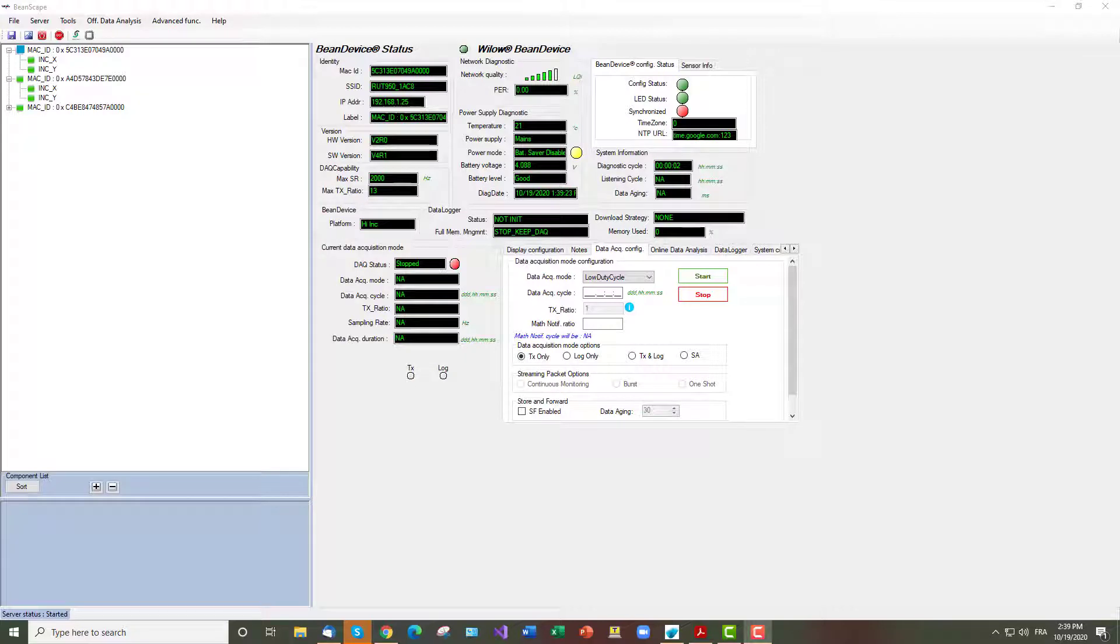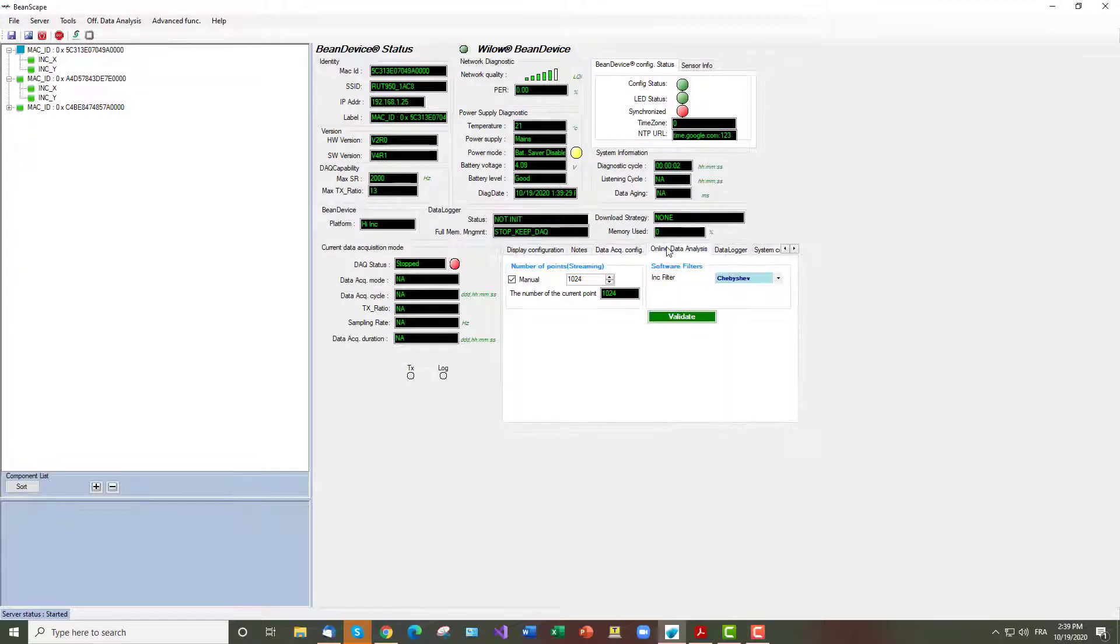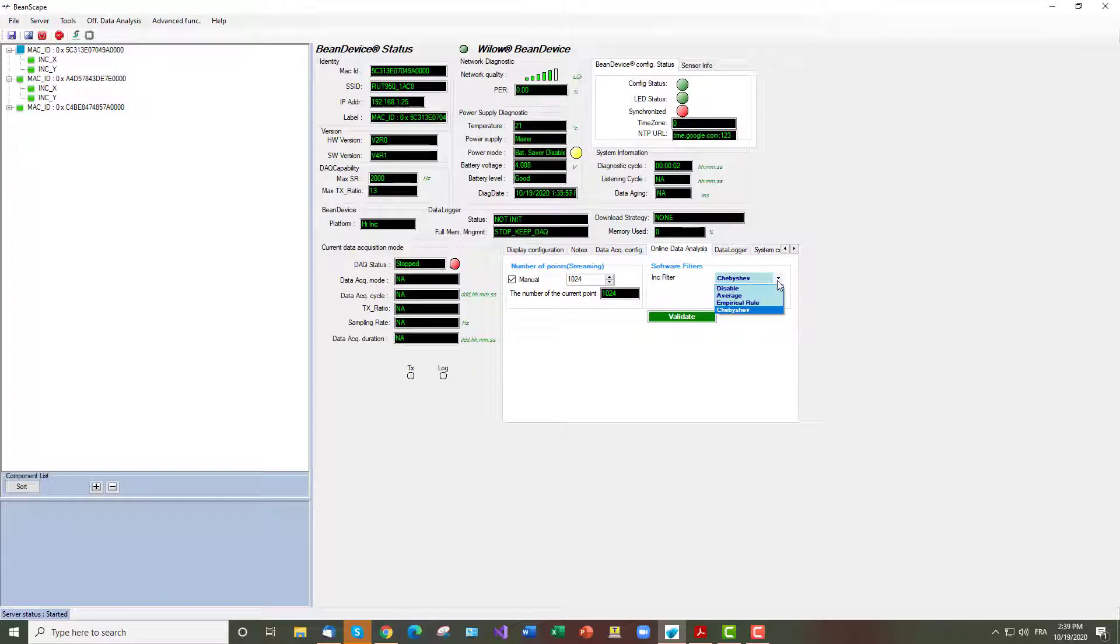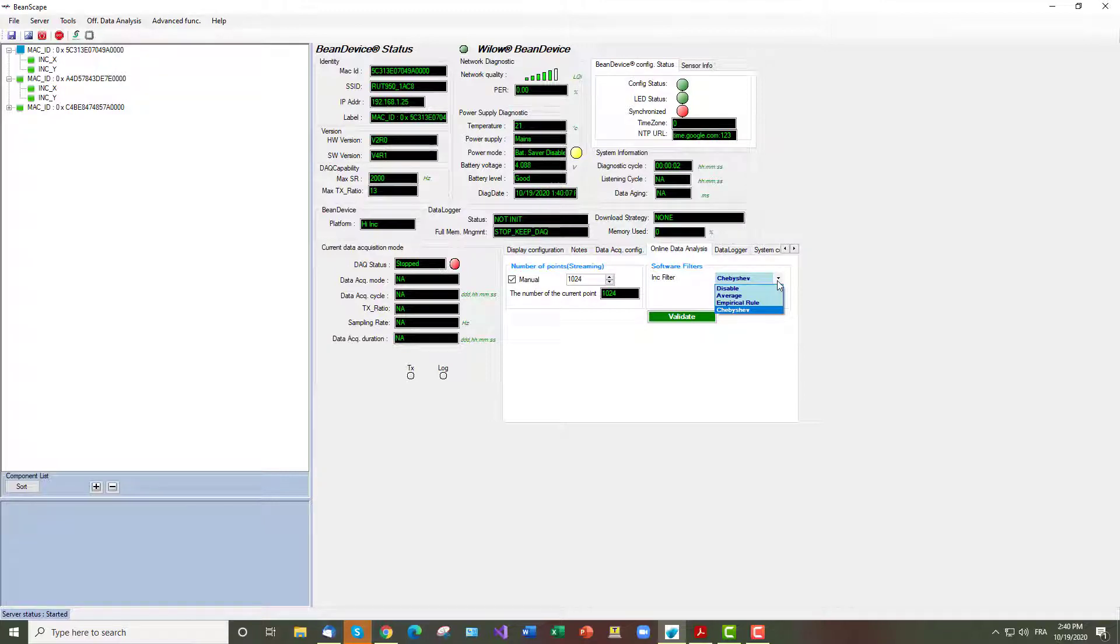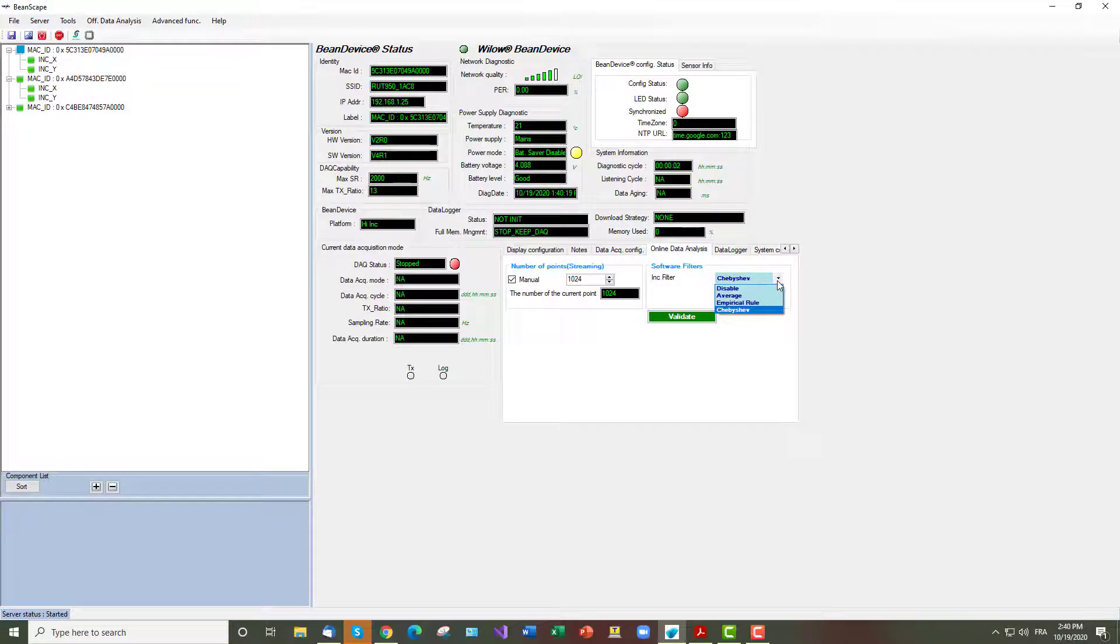Navigate to online data analysis tab and pick from the scroll down list. The following filters are used to reduce the noise and shock impact on the signal. For the average filter we have some restriction such as the filter will be applied only if the peak to peak value is higher than 0.1 degree. For example, we will pick the Chebyshev filter, then we change the number of points to manual in order to get the graph instantly.